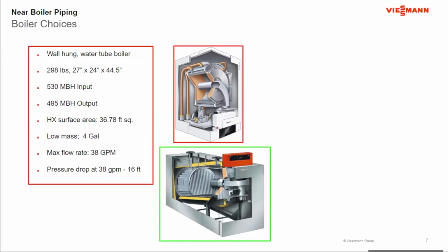The maximum flow rate is 38 gallons a minute, and at 38 gallons per minute, it's about 16 feet of pressure drop across the boiler. So when we start to look at that boiler, that's what that represents based on the design criteria. It has to be compact, and you should be able to hang it on the wall.